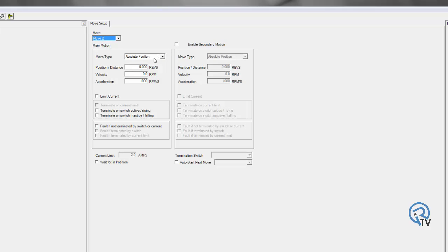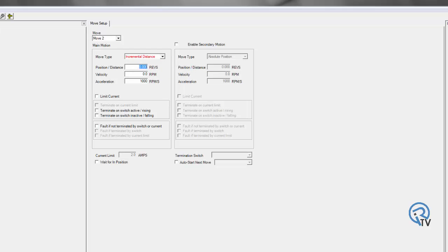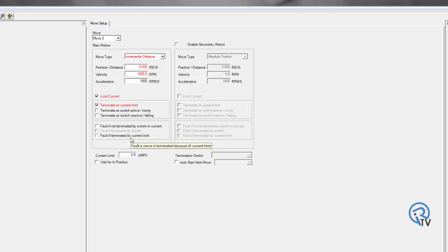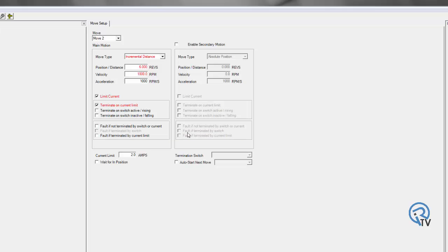Move two. I'm going to set that up as an incremental distance. I'm going to go six inches, 1000 RPM. But I also want to limit my current. So as this actuator is extending, I'm going to limit my current to two amps. So if I were to hit a hard stop, this drive would actually stop. And before it may or may not get to my six inches, I can say terminate on my current limit, or I can terminate this to a switch. I can also fault the drive out if this did not terminate to a switch or current, or if it did not terminate to a current limit.